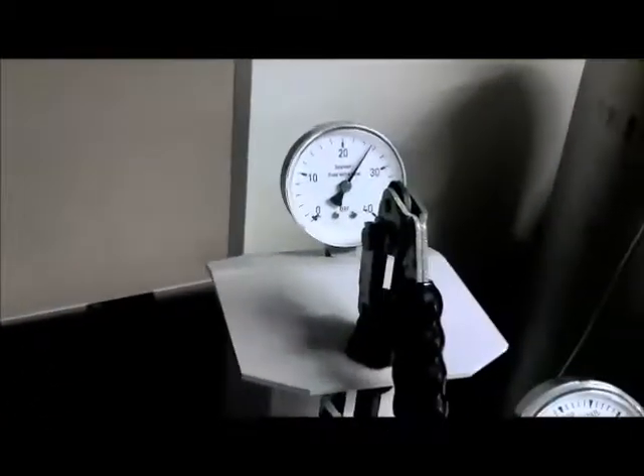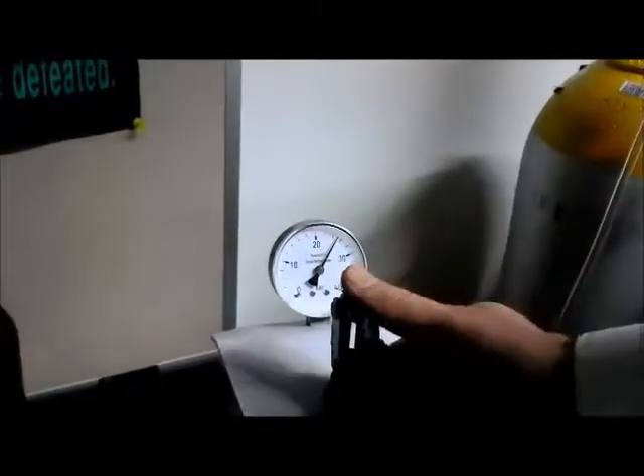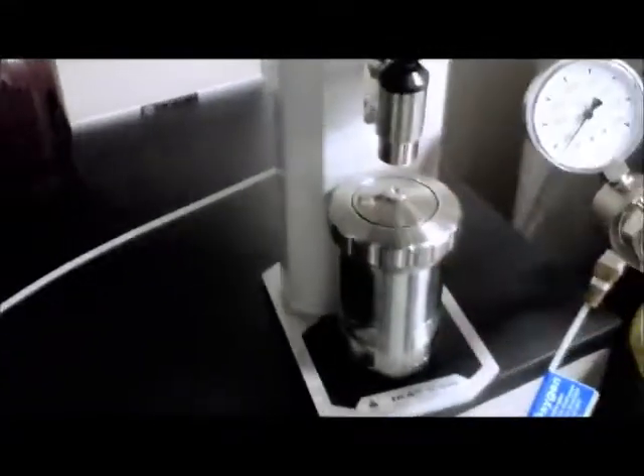Is this part two of the calibration? Does it matter how much it is? It does. They require that you put 25 bar, so you try to get it as close as possible. Once it's steady at 25 bar, you can lift this handle up. You'll hear a snap. That's the valve on the bomb closing.